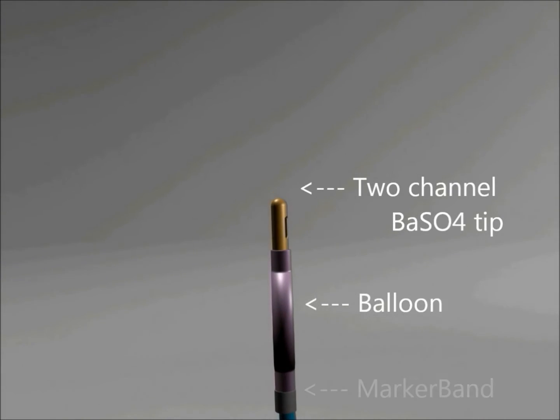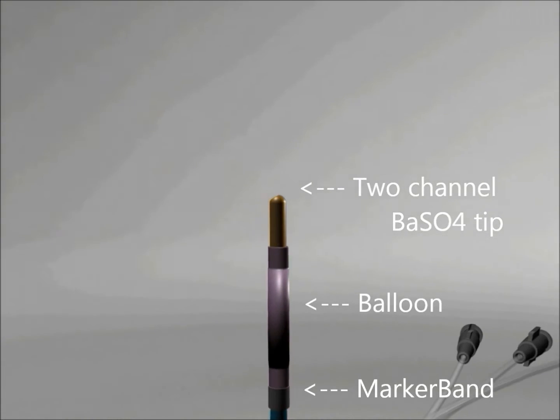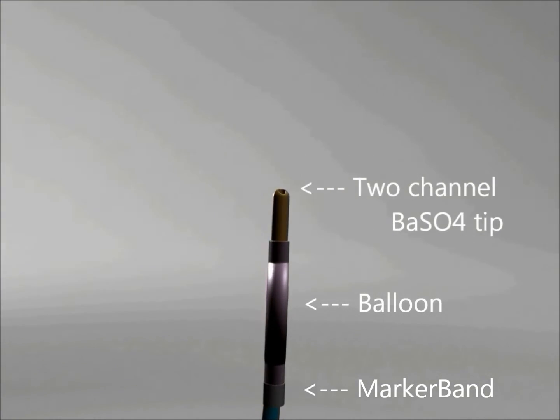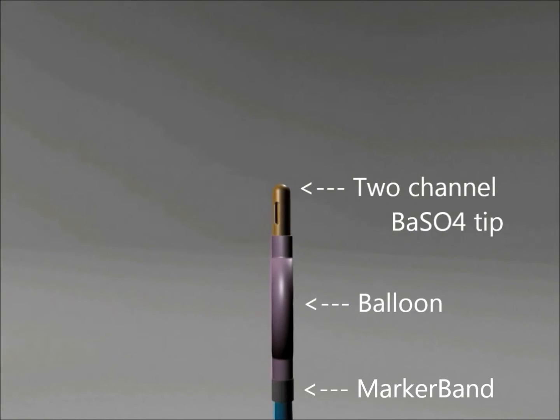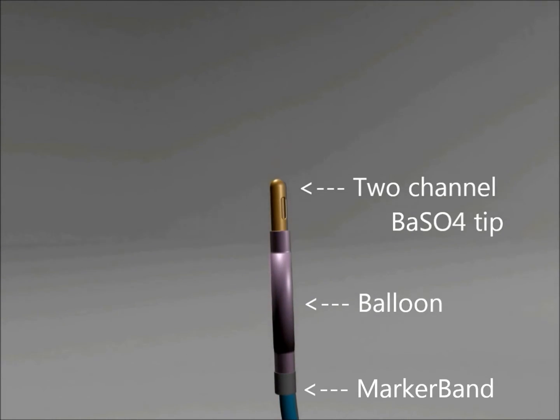The design of the two-channel tip and catheter shaft has been chosen specifically to reduce kinks and unwanted interactions with vessel walls. The integrated two-channel barium sulfate tip and use of one marker band allows physicians to clearly observe where the catheter is inserted via fluoroscopy.